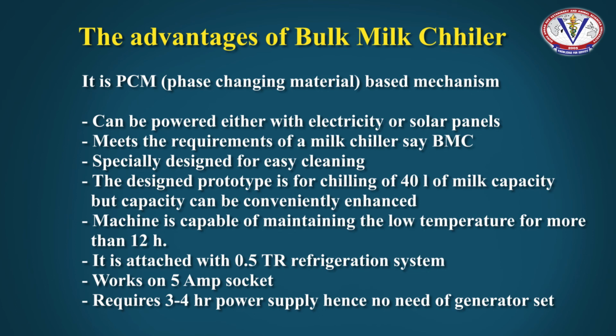Another advantage is that most villages don't have a 24 hour power supply, hence it is very much required that at the time of milking, whether in the morning or in the evening, the power supply must be there to run the conventional bulk milk chillers. But with secondary refrigerants or PCM based systems, this requirement of having electricity supply at the time of milking was eliminated, and also the use of generators in the absence of electricity has been eliminated. So the application of PCM based refrigerants for milk chilling is of utmost importance in countries where there is no power surplus.